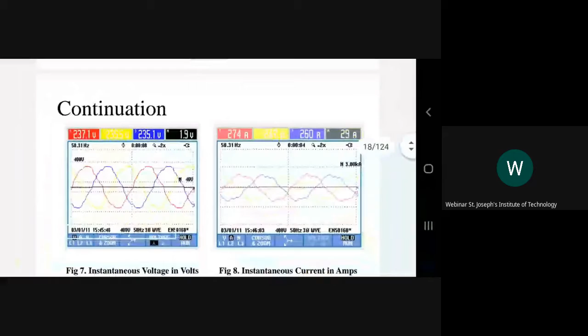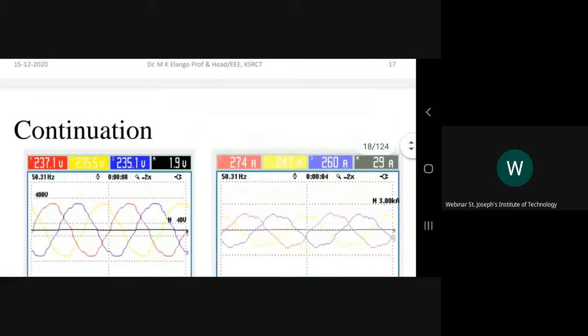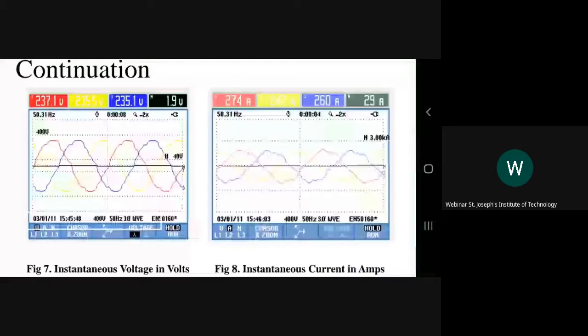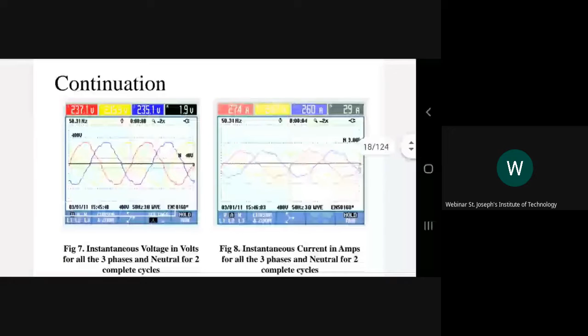In this textile mill there are 6 units. At the time of measuring power quality with the power quality analyzer, only 4 units were running, and under these 4 units it consumes 274 ampere. Imagine if all 6 units were running, what current rating would be drawn from the bus bar. So this is the instantaneous current in amps for all three phases and neutral, for two complete cycles.